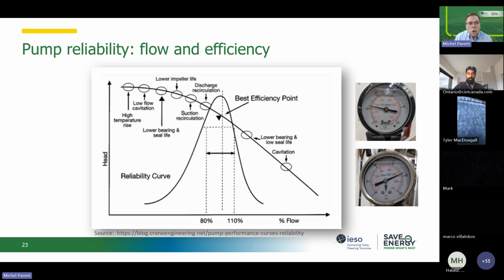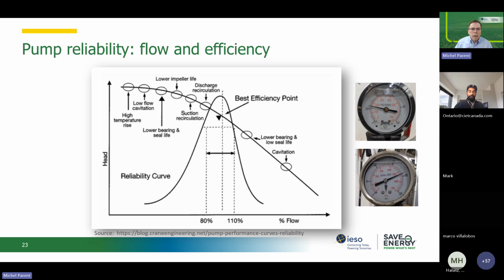But the best efficiency point is also the best reliability point. So on this graph, what you see is what happens to the reliability of your pump when you are not running where it's supposed to be running, which is its best efficiency point. Pumps will always be selected for a given application to run at their best efficiency point. To give you an example, you read on those gauges 60 psi, and that 60 psi is way lower than the actual design head. Let's say the design head was 80 psi, you're running at 60 psi. What happened is you're moving from here, you're moving down here, and your flow is going to increase because your head is lower. And the consequence of that is your bearing life will go down and you'll have a leakier pump. The seal of the pump will also not last as long.